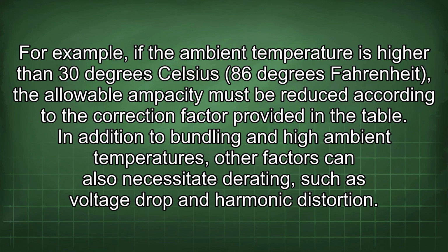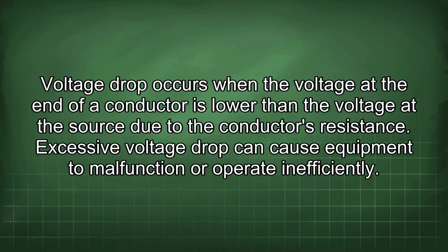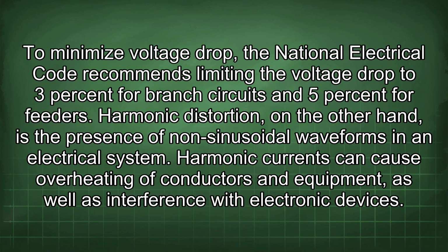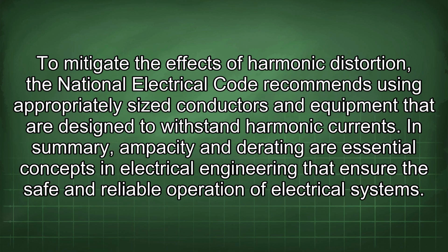In addition to bundling and high ambient temperatures, other factors can also necessitate derating, such as voltage drop and harmonic distortion. Voltage drop occurs when the voltage at the end of a conductor is lower than the voltage at the source due to the conductor's resistance. Excessive voltage drop can cause equipment to malfunction or operate inefficiently. To minimize voltage drop, the National Electrical Code recommends limiting the voltage drop to 3% for branch circuits and 5% for feeders. Harmonic distortion, on the other hand, is the presence of non-sinusoidal waveforms in an electrical system. Harmonic currents can cause overheating of conductors and equipment, as well as interference with electronic devices. To mitigate the effects of harmonic distortion, the National Electrical Code recommends using appropriately sized conductors and equipment that are designed to withstand harmonic currents.